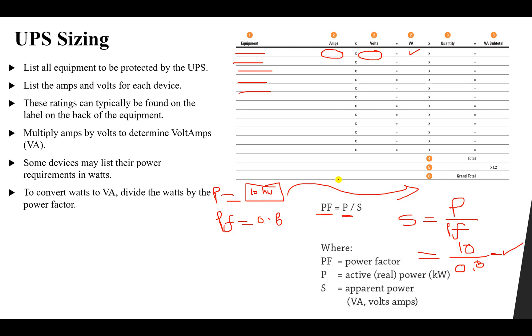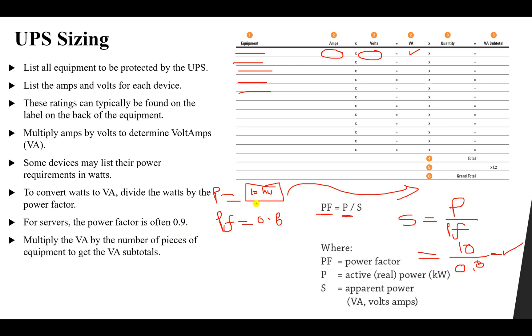To convert watts to volt-ampere, divide the watts by the power factor. For servers, the power factor is often 0.9. After getting the volt-ampere for each piece of equipment, multiply it by the quantity — for example, if you have three units of a 20 kVA device, multiply 20 kVA by 3 to get the total volt-ampere for that equipment type. Then add all the volt-ampere totals together.